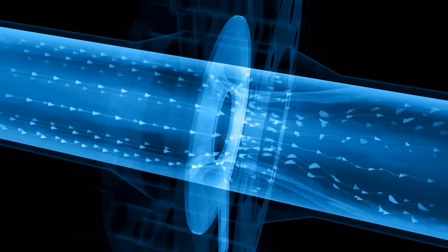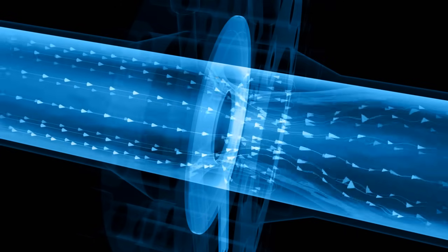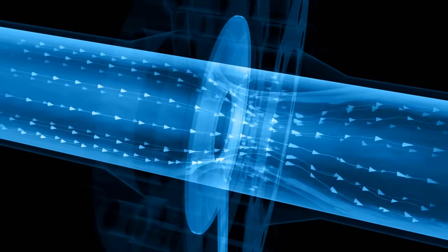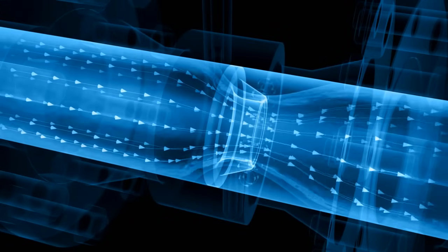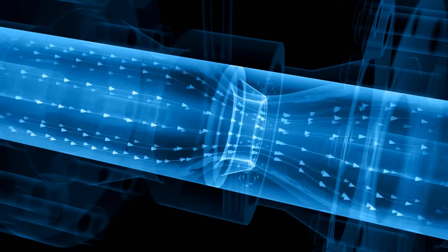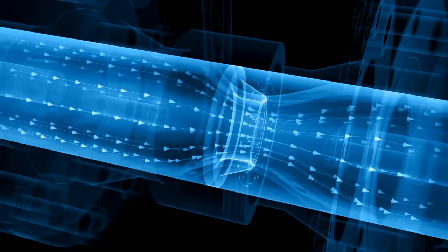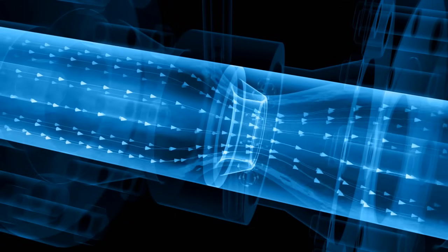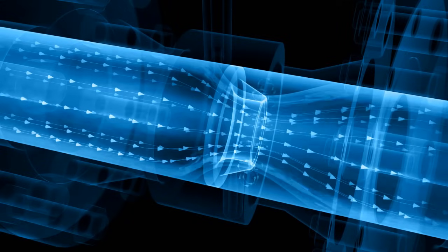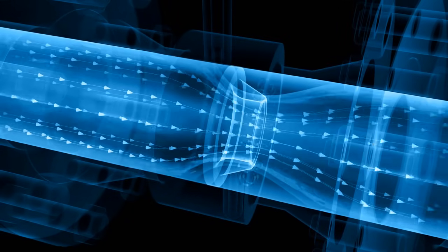This demonstration shows that an abrupt restriction generates severe turbulence in a fluid. Nozzles with a rounded, funnel-like inlet clearly reduce turbulence and thus create less pressure loss. Nozzles are particularly suitable for higher flow velocities or fluids with abrasive solid particles.